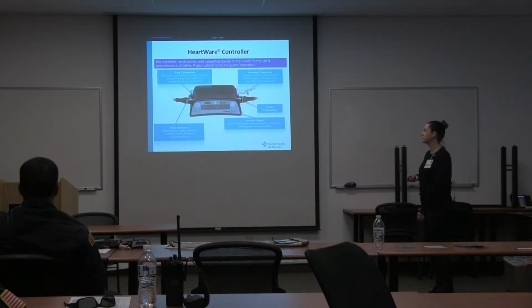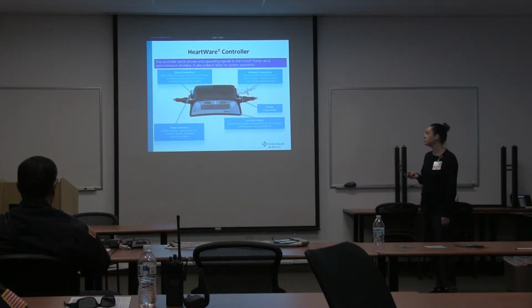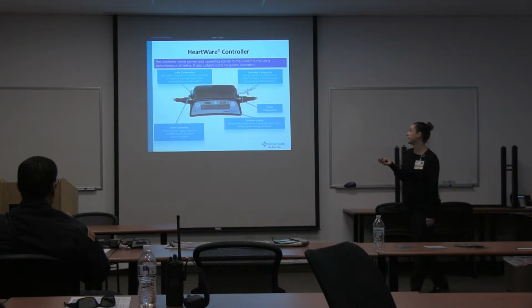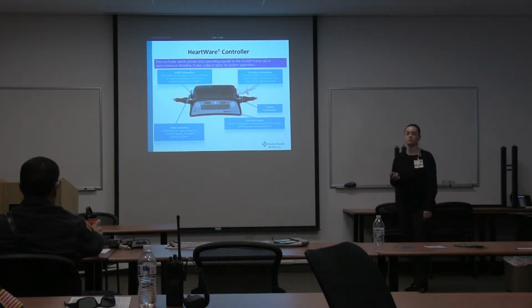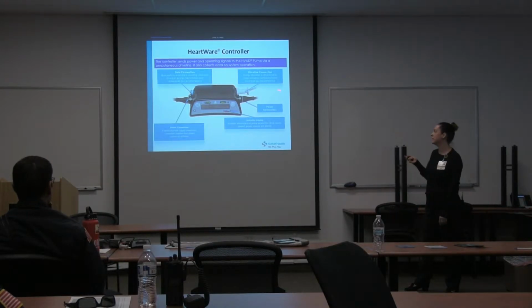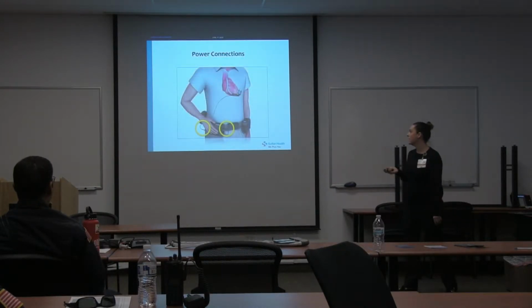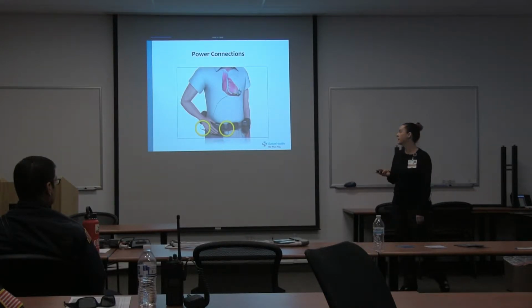So it tells you right on the screen what the possible resolution to the alarm is. They also have power connections coming off of either side of the controller. So if you ever come in contact with a patient, they should always have 2 power sources connected. And this is their drive line that goes into the side of the controller. That should never be out of the side of the controller ever. And this is what their connections look like connected to their controller as they're walking around up and mobile throughout the day.